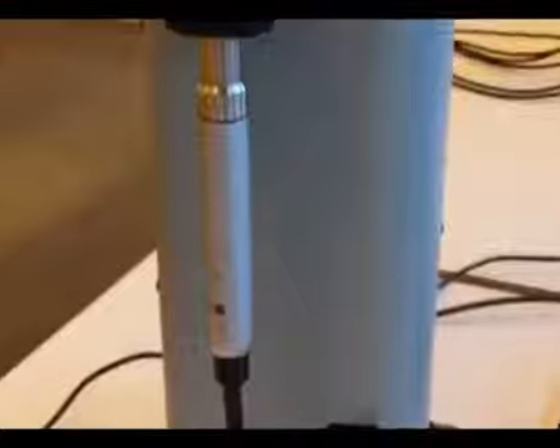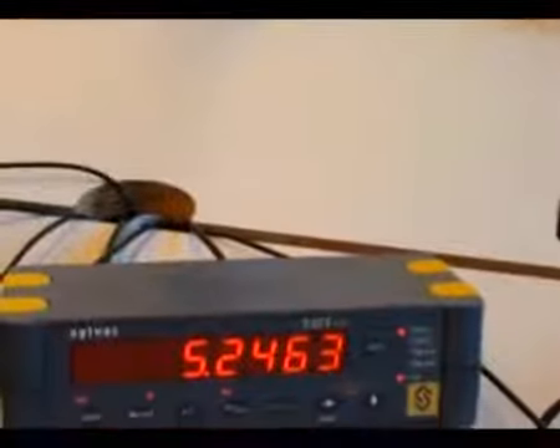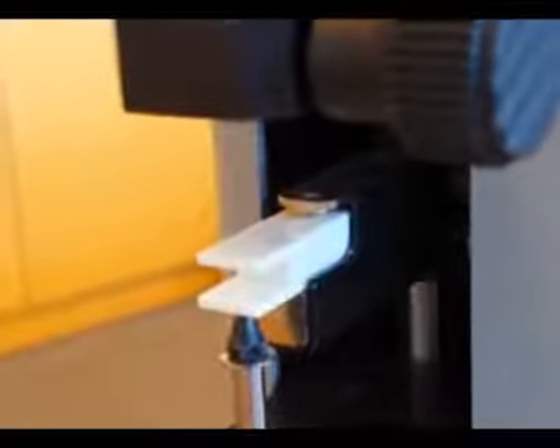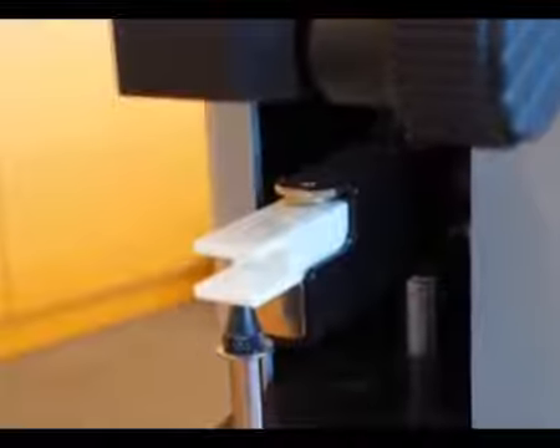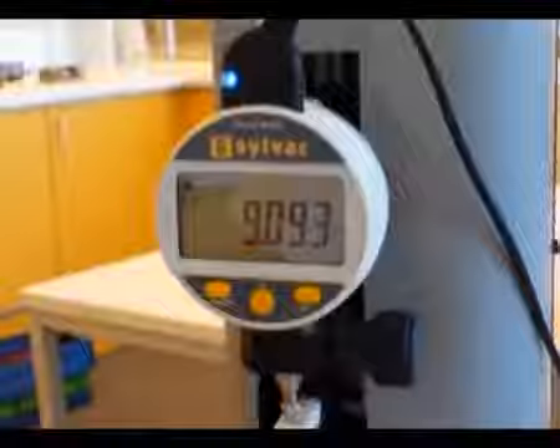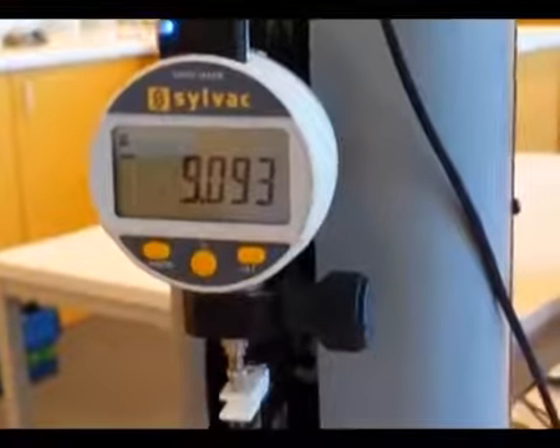The M3 kit is a dial gauge calibrator which is delivered with a Sylvac measuring system, a high accuracy probe, which is connected to a digital unit. This dial gauge calibrator has ceramic gauge blocks that make the transition between the probe, the master, and the instrument to be calibrated.